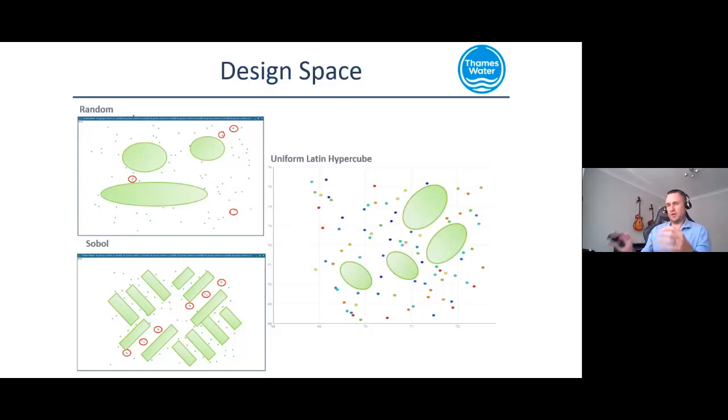And what we want to do ultimately is start manipulating the start levels of each of the pumps, so that by throttling it back, by saying don't start just yet, start a little bit later, and using that natural capacity within the network, we can reduce pump starts and reduce energy. We can treat this as a collective system. And that was what we did. So those 84 runs were allowed to run.